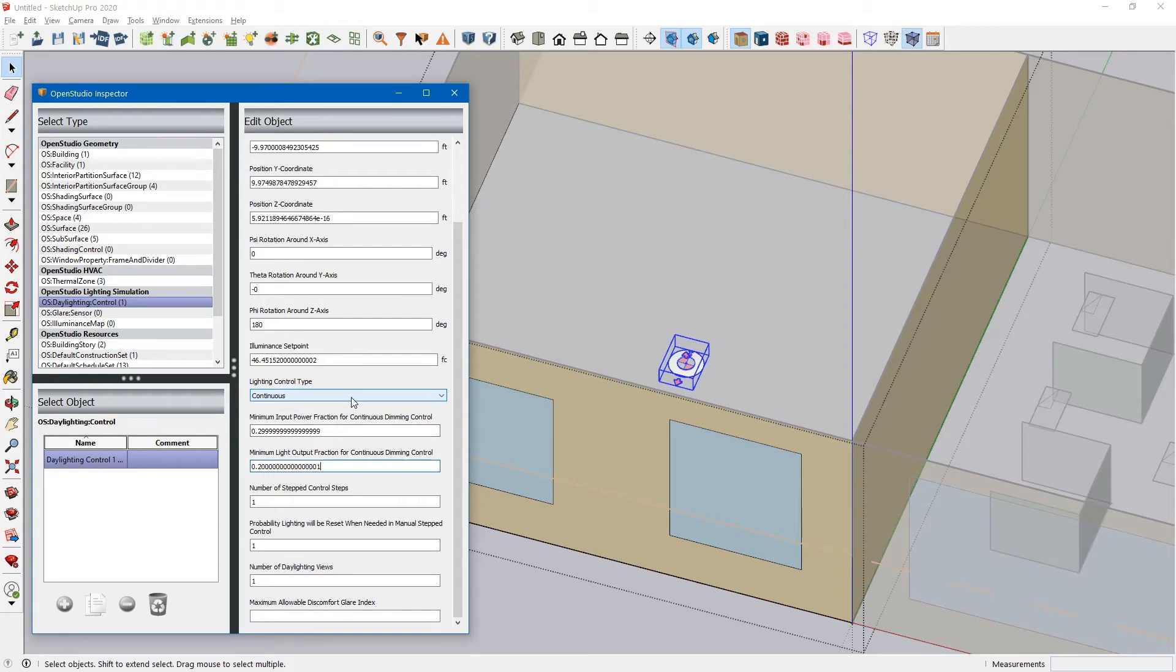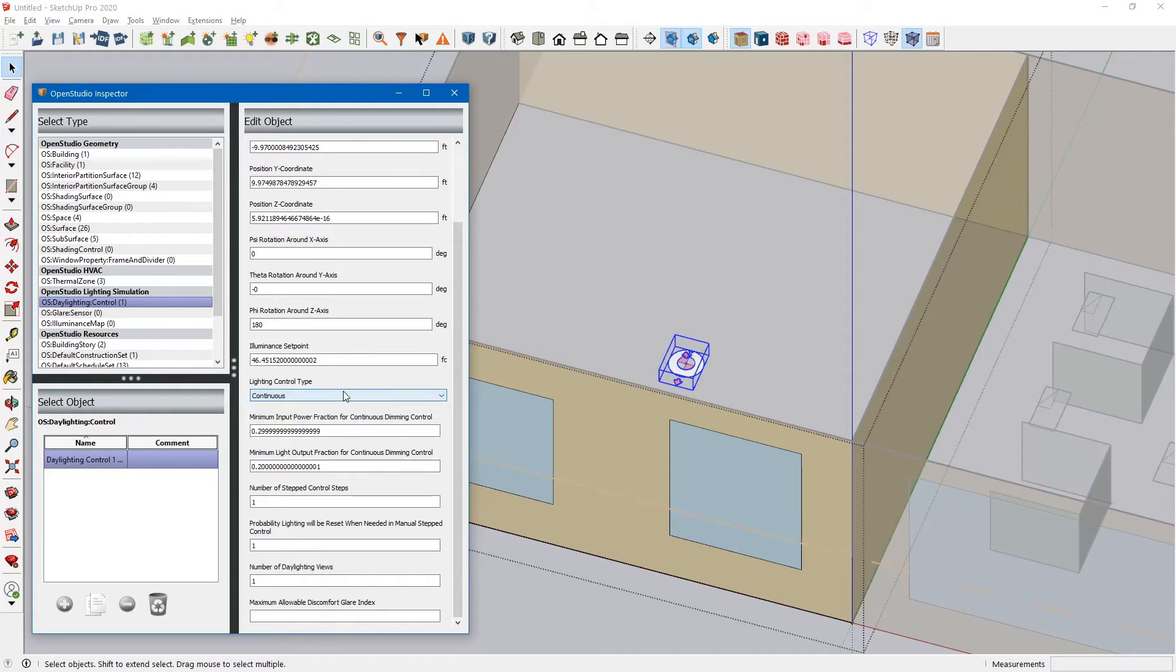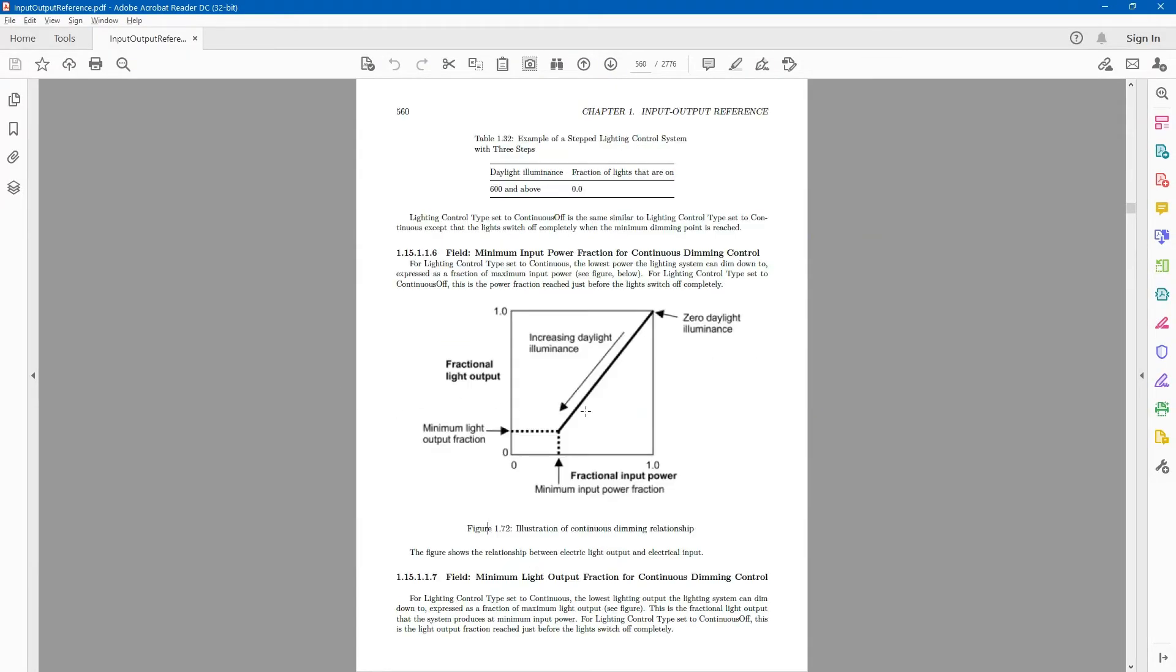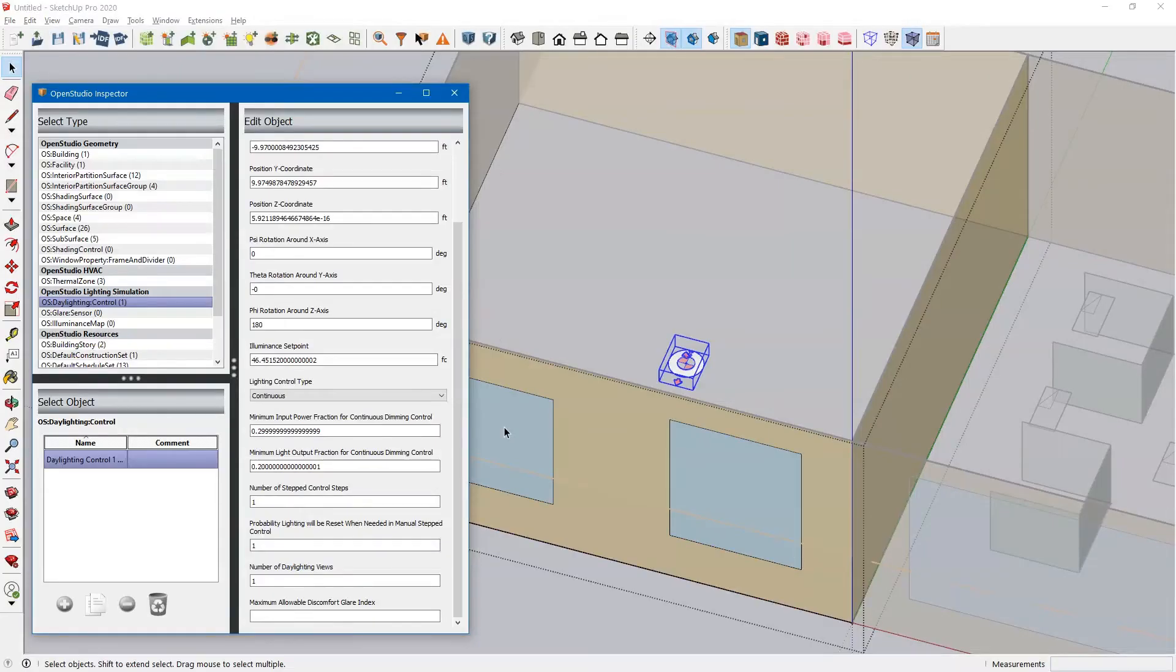The lighting control type can be selected here. Continuous. The continuous lighting control starts at your design illuminance. And then it continuously dims the lights until you get to a minimum input power fraction and minimum light output fraction, which are these values down here.